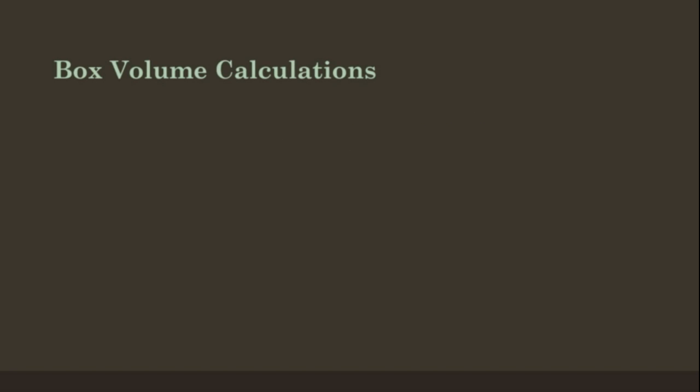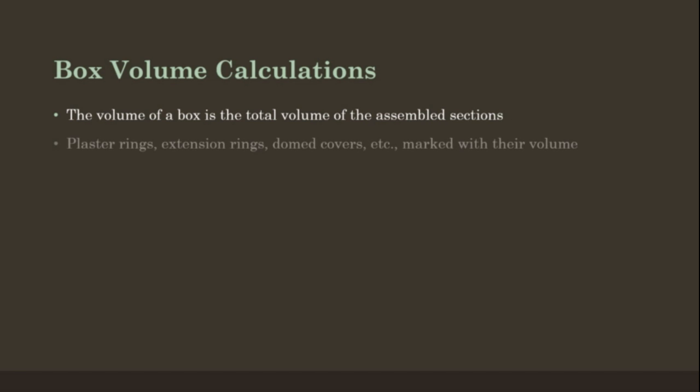Box volume calculations. The volume of a box is the total volume of the assembled sections. Plaster rings, extension rings, dome covers, etc. are marked with their volume.